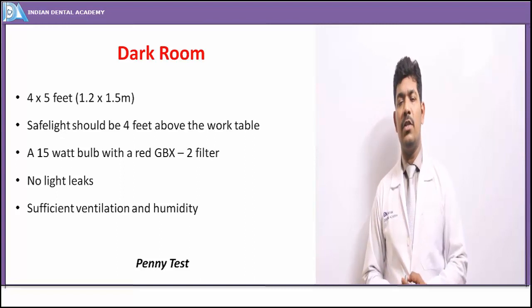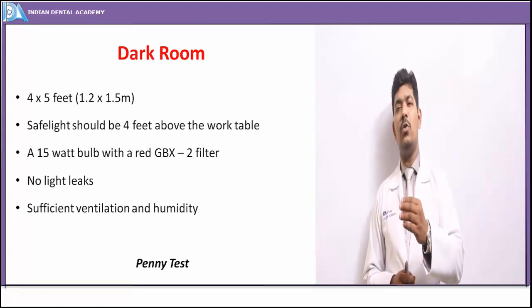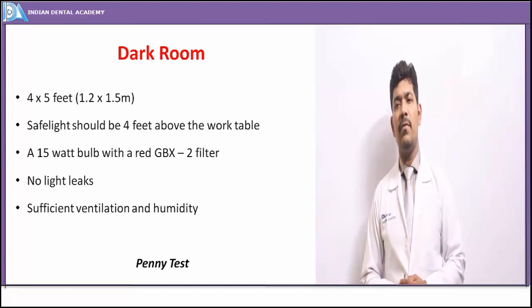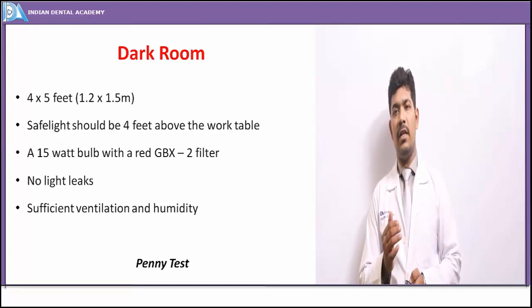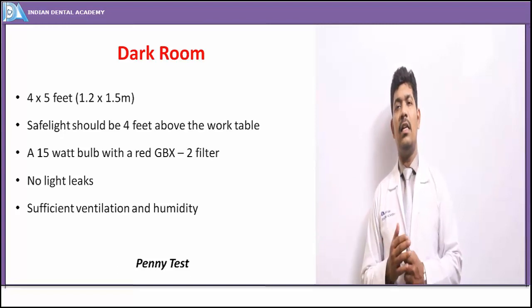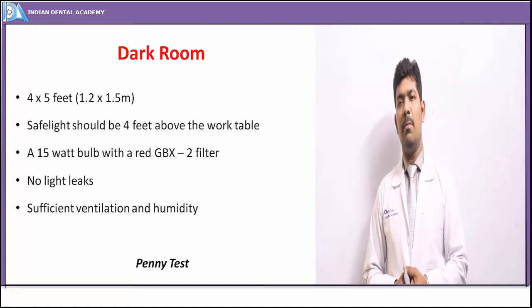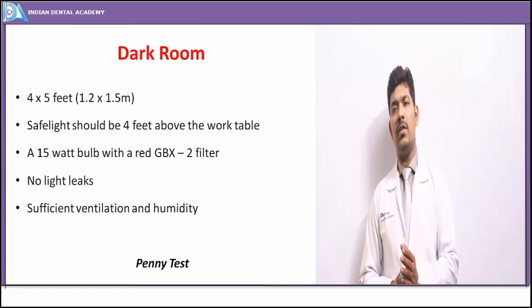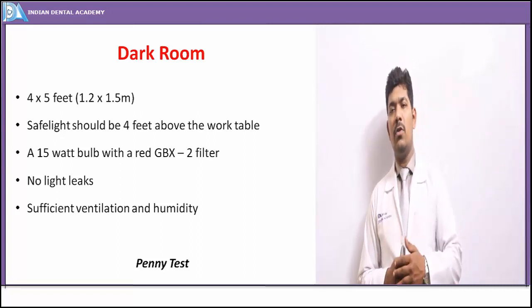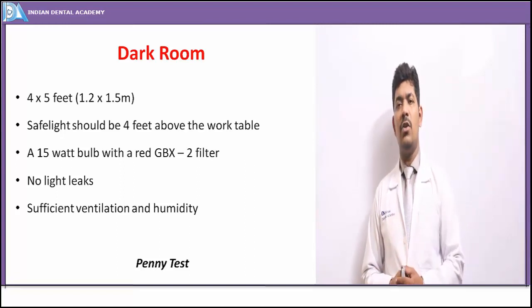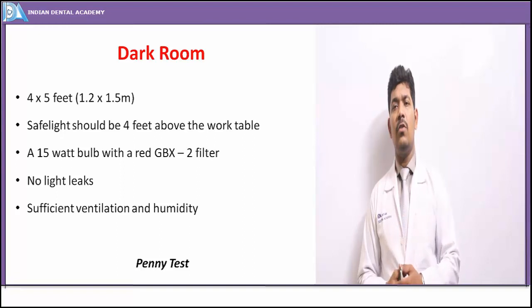The darkroom requires a safelight — a red 15-watt bulb with a red GBX filter — which has minimal effect on the image receptor, reducing the risk of accidental darkening. This safelight must be positioned at a distance of four feet above the working area. Most importantly, there must be absolutely no light leaks — all windows and doors must be totally sealed with black paper. Sufficient ventilation is also required to take out chemical fumes, along with adequate humidity control.